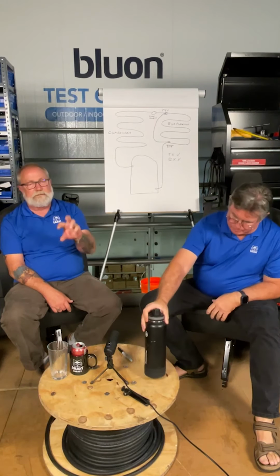Is superheat and subcooling the same in the winter on a heat pump? The big difference is that in the winter, you're going to be working off of the outdoor metering device, because you're absorbing the heat in the outdoor coil and you're having free flow through the indoor coil, so you're bypassing the metering device on the indoor coil. Yes, because your liquid line is still your liquid line, but your suction line is no longer your suction line, it's the discharge line. If you wanted to calculate superheat and subcool, you have to know the head pressure and the liquid temperature, and you also have to be on the suction side of the reversing valve, as well as having your gauge on the true suction line on the unit.